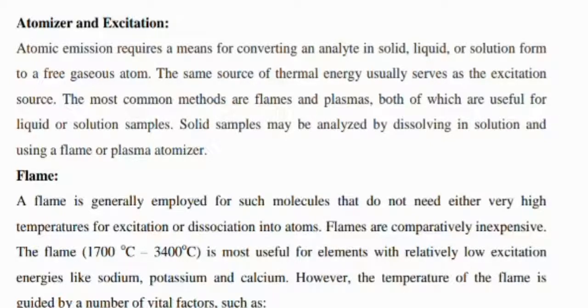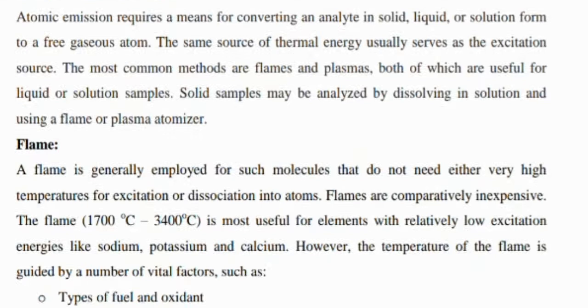into atoms. Flames are comparatively inexpensive, and the flame temperature of 1700 to 3400 degrees Centigrade is most useful for elements with relatively low excitation energies.